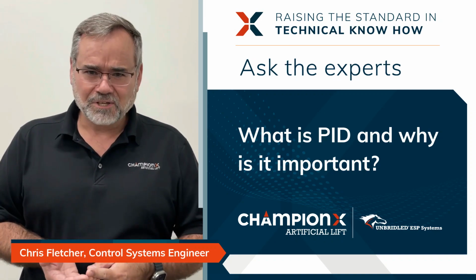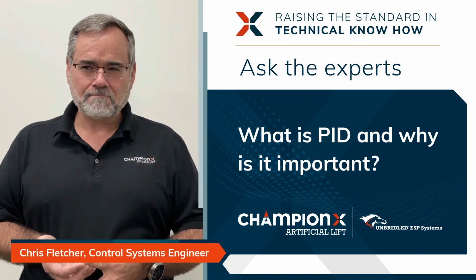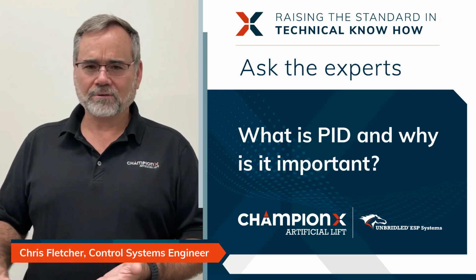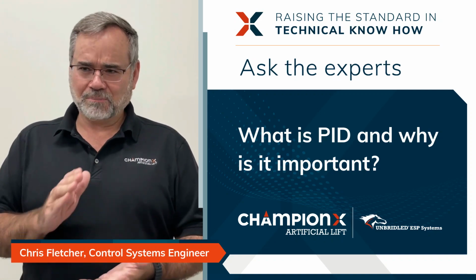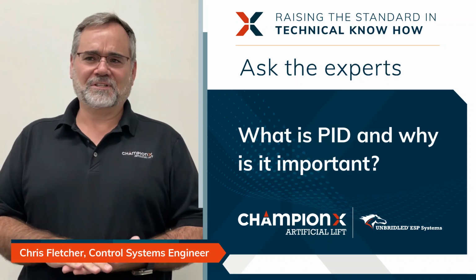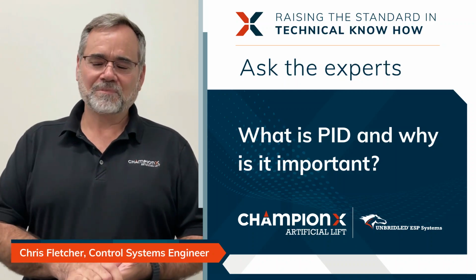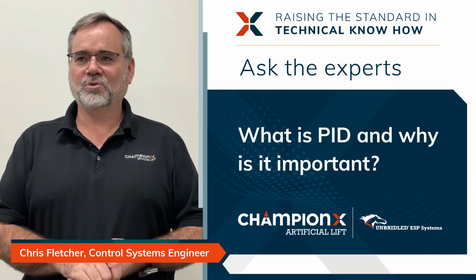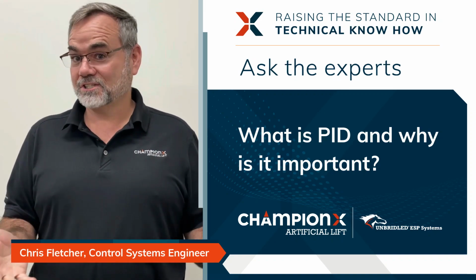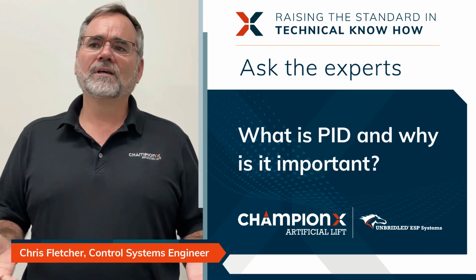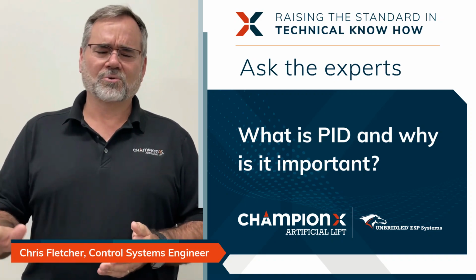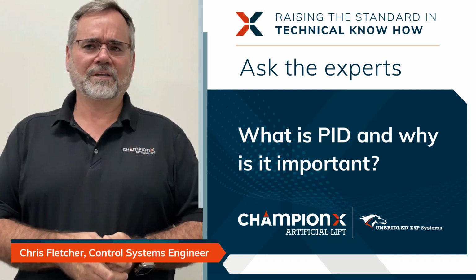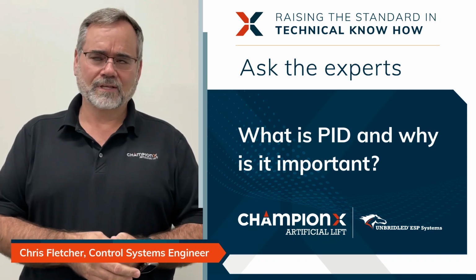Let me tell you a secret: most of the time, don't use the D part. You don't need it. Just use the P and the I, because the D is just going to mess you up. The D does what's called noise amplification. If there's noise in the signal, the D is going to make it worse. So for most things, just ignore the D. You might use it for temperature control, but that's probably about it.